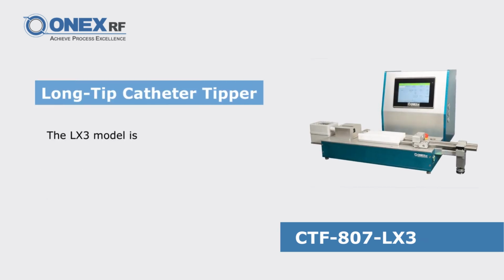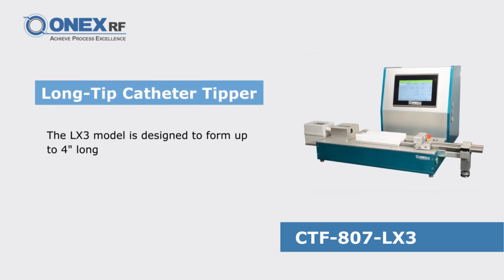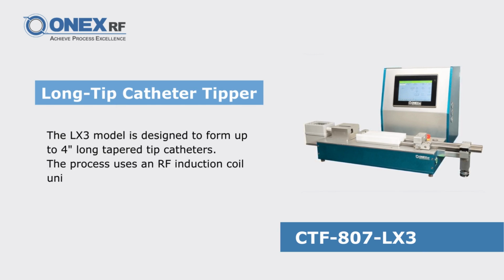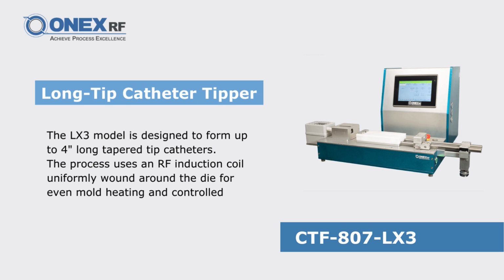The long-tip catheter tipper is designed to form up to 4-inch long tapered tip catheters. The process uses an RF induction coil uniformly wound around the die for even mold heating and controlled plastic formation.